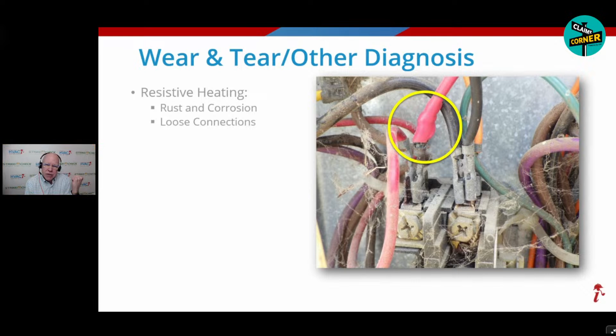Here's another one, loose connections. Same thing - electricity is being slowed down by the loose connection. See that wire that's deforming there and receding, melting 1 to 2 inches within a connection, loose or rusty. This one's actually rusty too, rusty and loose. Not lightning, not surge. If that was a good connection, lightning or surge would flow right through it. It wouldn't know to stop there and cause damage. It causes damage when it can't go any further, like endpoints, like motors. All right, that's resistive heating.